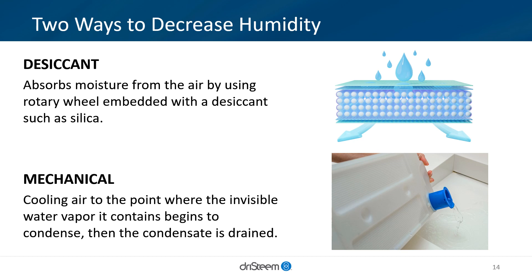When you need to decrease the RH, you can choose between two dehumidifier technologies: desiccant and mechanical. Desiccant dehumidification absorbs moisture from the air by using a wheel embedded with a substance that absorbs water and promotes drying. Mechanical dehumidifiers cool the air to a point where the invisible water vapor it contains begins to condense, then the condensate is drained. Typically application requirements determine the technology used. Desiccant dehumidification is more effective in cooler temperatures, whereas mechanical dehumidifiers work best in warmer temperatures.